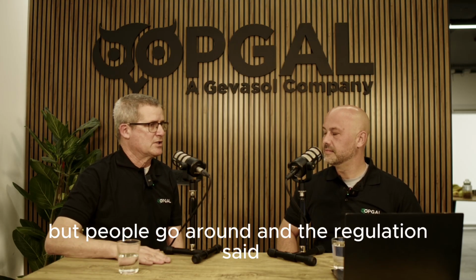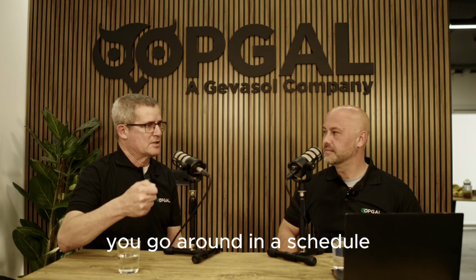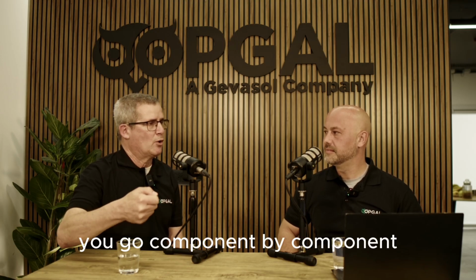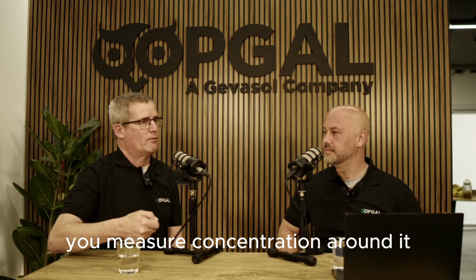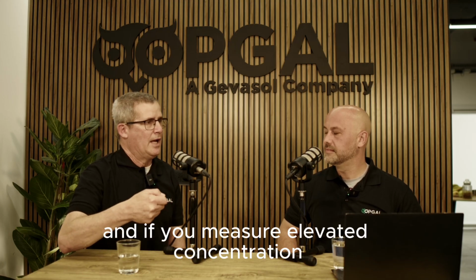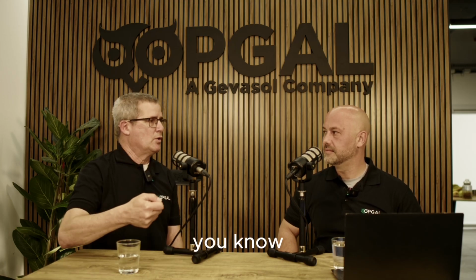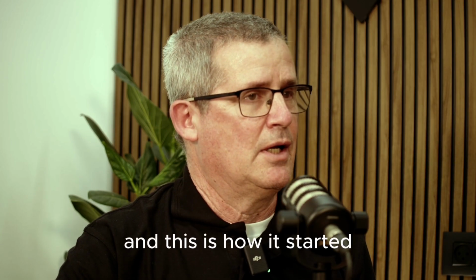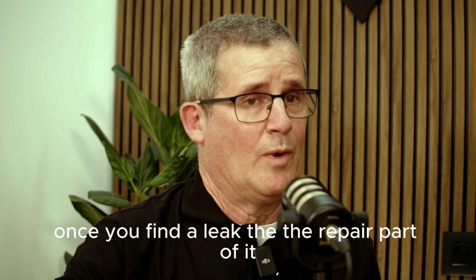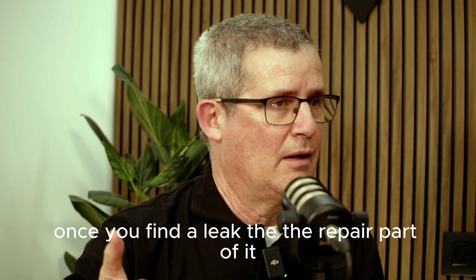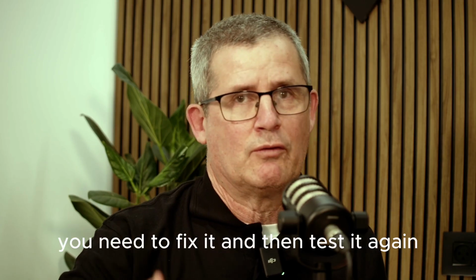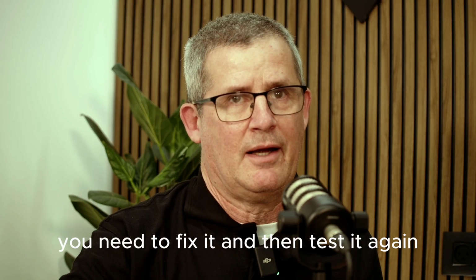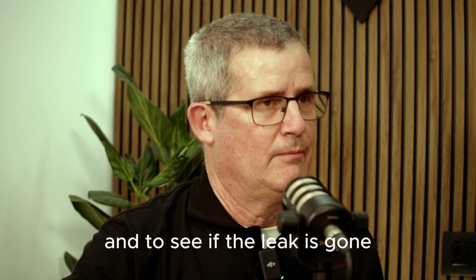People go around, and the regulation said you go around on a schedule, you go component by component, you measure concentration around it, and if you measure elevated concentration, you know you have a leak from somewhere in this vicinity. And this is how it started. And once you find a leak, the repair part of it, you need to fix it and then test it again to see if the leak is gone.